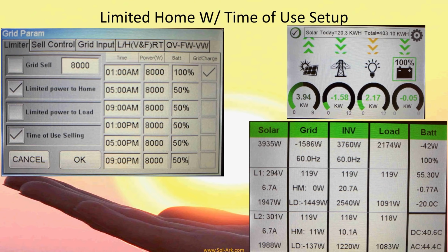Here's where we talk about programming limited power to home. What this does is sell back to the rest of the house. Here's an example: I've got my loads consuming about 2 kilowatts, and the inverter is actually pushing back to the rest of the household about 1.6 kilowatts because it's trying to cancel out other loads. So at the inverter side we see about minus 1.6 kilowatts, but our home sensors read somewhere between 0 and 30 watts. So it's canceling out the entire home grid.